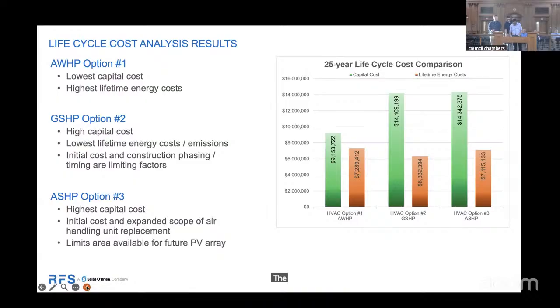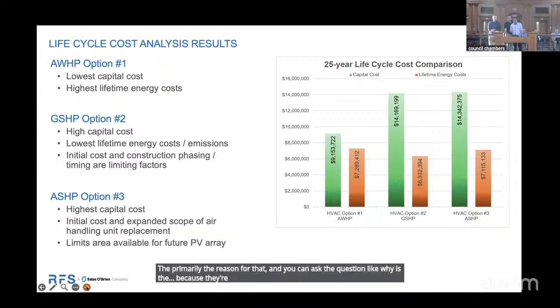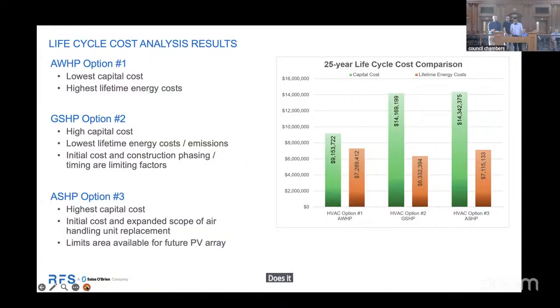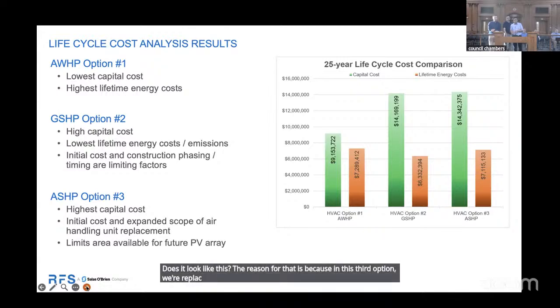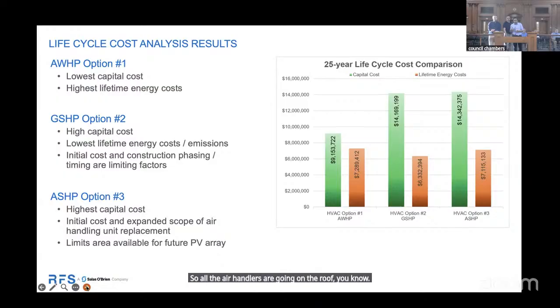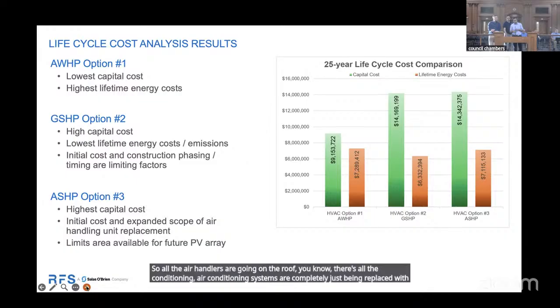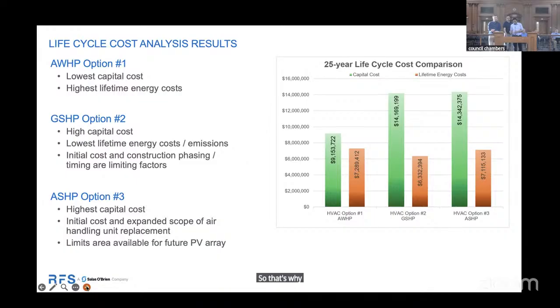You might ask why, since the air source heat pump and air-to-water source heat pump are very similar technologies. The reason is that in this third option, we're replacing a lot of equipment—all the air handlers are going on the roof, and all the air conditioning systems are being completely replaced with new ones. That's why the capital cost is so high for this option, while the energy cost is slightly lower.